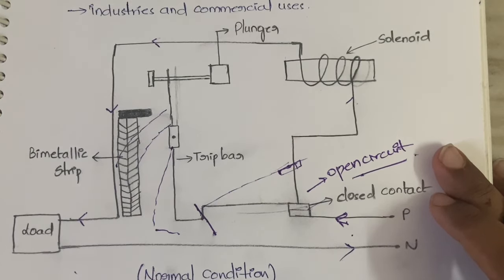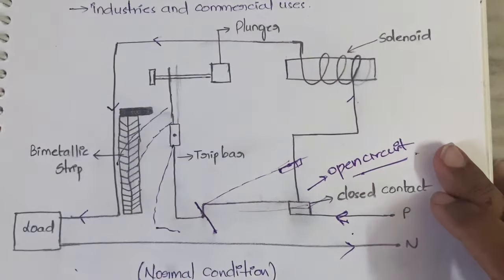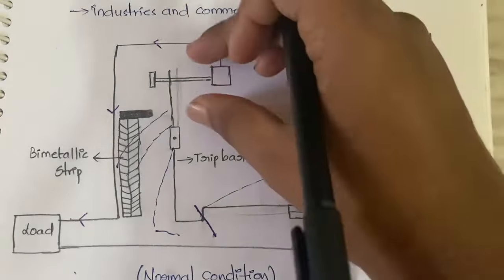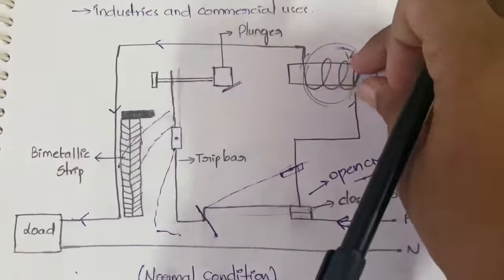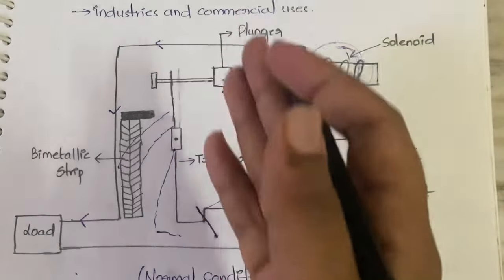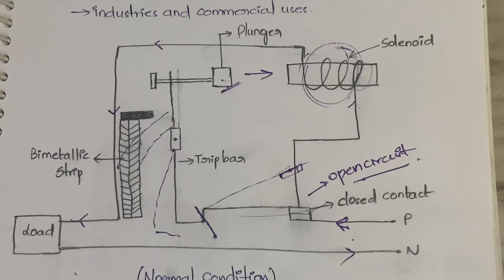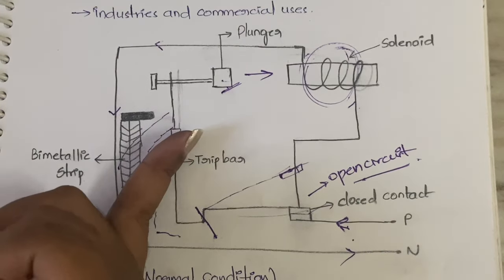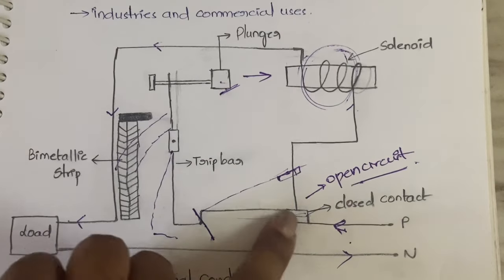When there is a sudden increase in current, the solenoid has metal windings, and because of them a magnetic field is generated inside and around the solenoid. Because of this magnetic field, the plunger — which is made of metal — is attracted towards the magnetic field. When the plunger is attracted, it gets displaced, and since the plunger is connected to the trip bar, the trip bar also gets disturbed.